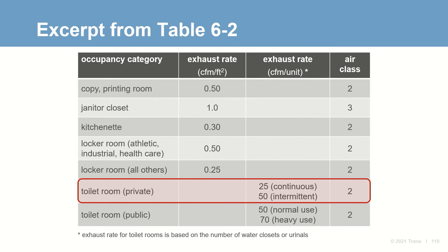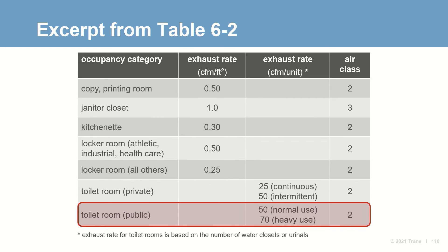Note that for toilet rooms, the exhaust rates are based on the number of water closets or urinals installed. A private toilet room is intended to be occupied by only one person at a time, with a lower rate of 25 CFM allowed if the exhaust operates continuously; otherwise, the higher rate of 50 CFM is required if the fan turns on with a light switch. For a public toilet room, the lower rate of 50 CFM per unit is permitted, but the higher rate of 70 CFM is provided where periods of heavy use are expected.